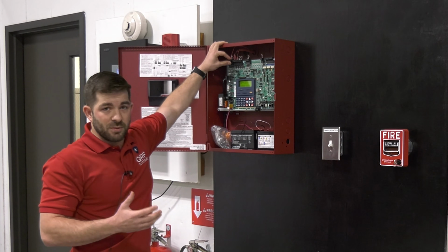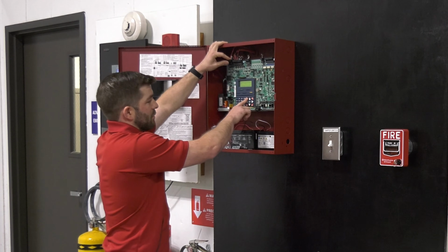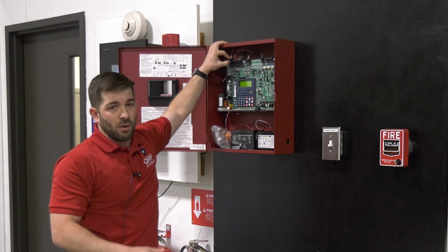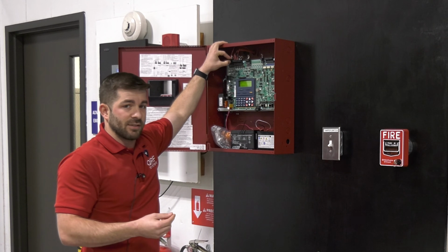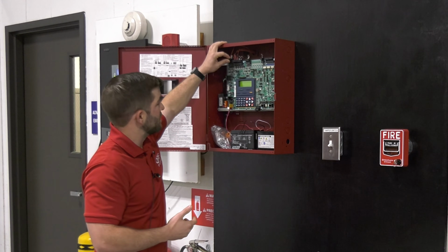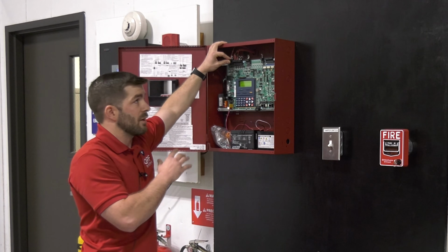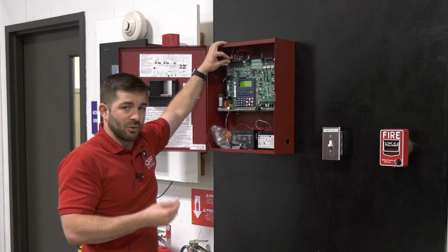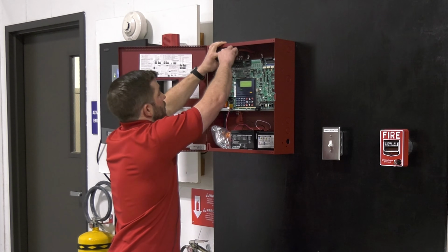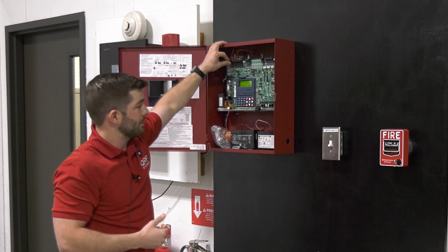Now, if this was a panel and you were doing an inspection, let's say you pulled a NAC circuit, here I'm going to silence this. If you pulled a battery, pulled a horn strobe off the wall, the panel has up to 200 seconds to enunciate. If it doesn't, it fails. Same thing as clearing a trouble. If a trouble's present and you bring whatever state was in trouble back to normal, it has 200 seconds for the panel to clear. Now I'm going to put this back. There it goes, it clears.